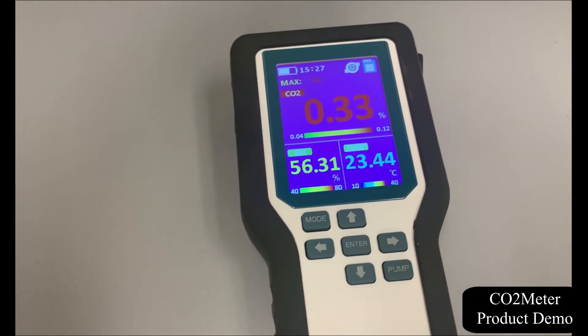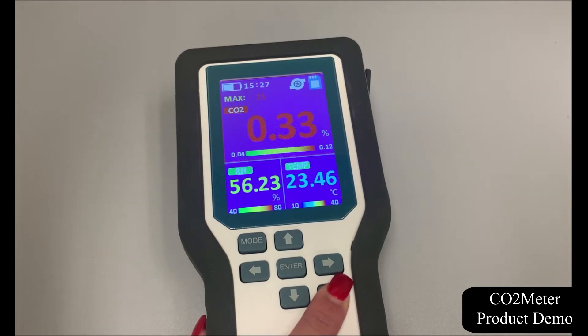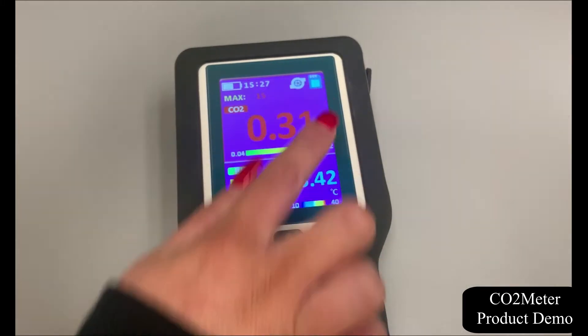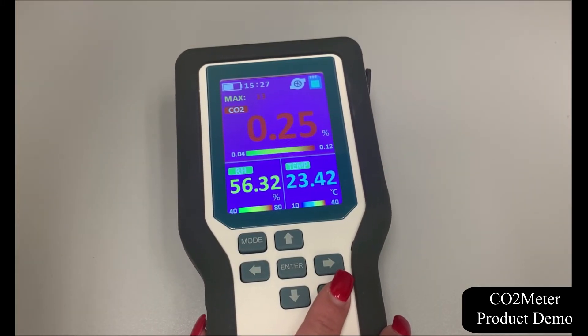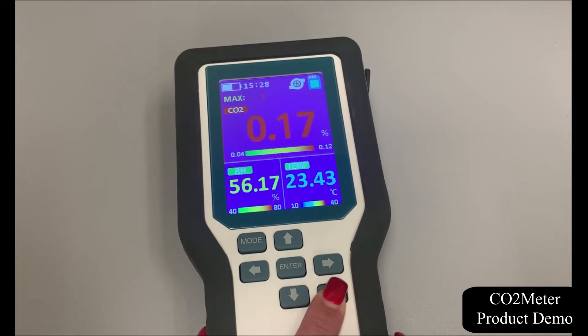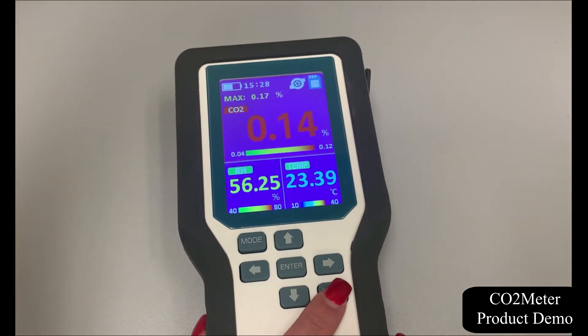To begin recording the data, place the meter in a suitable location and connect the tubing and filters as required. To begin logging, press and hold the pump button until the SD card icon changes its inner color to green — this means the CM1000 is recording data. When the SD card is blue with a green interface, the pump will run continuously. To stop your logging, press and hold the pump button until the SD card icon changes color to a white interface. Once the SD card is white, the data is not being recorded, and the pump will stop after 60 seconds.